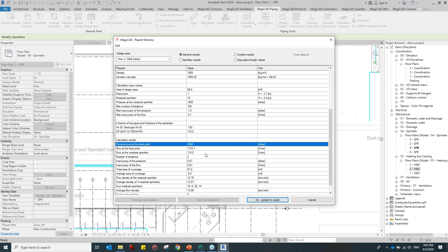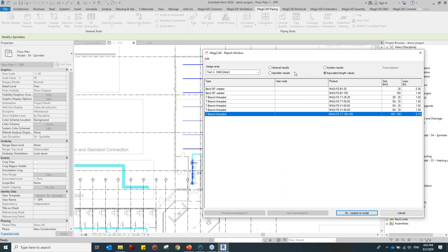If it's adequate, I can go for it, or otherwise I can resize the sprinkler network using different methods and recalculate the required capacities. You can also see the 4 weakest sprinklers, the sprinkler results, and the equivalent length values.